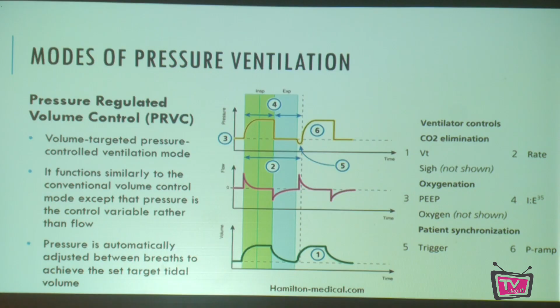Pressure is automatically adjusted between breaths. Every few breaths or so, it'll adjust the amount of pressure that it's providing to the patient to reach that set tidal volume. So we can set our tidal volumes to be lung protective at 6 mLs per kg, and then depending on the patient's effort, it's going to adjust the pressure that it's providing to the patient to reach the set tidal volume. So you'll notice in the graphics on the side, it looks like a pressure control mode rather than a volume control mode.